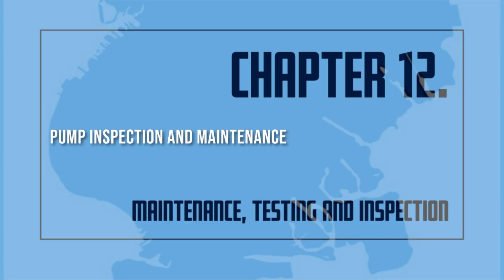The centrifugal pump relies on the water supply for cooling and lubrication and should never be operated without the pump being supplied with water. A visual inspection of all parts of the pump and the controlling equipment should also be conducted each week. This inspection should include the condition and reliability of the power supply. If any problems are discovered with the equipment, immediate action should be taken to correct the problem. Fire pumps should be fully tested annually to make sure that the pump, driver, power supply, and all other parts are functioning properly.